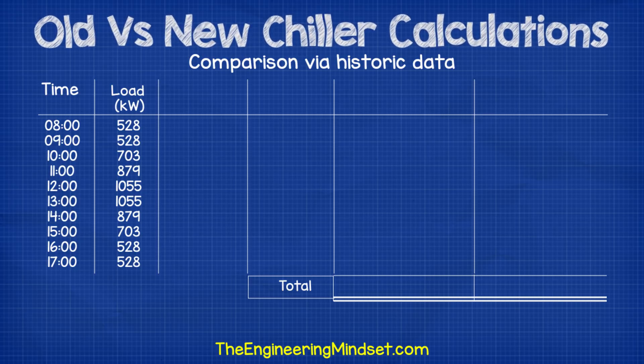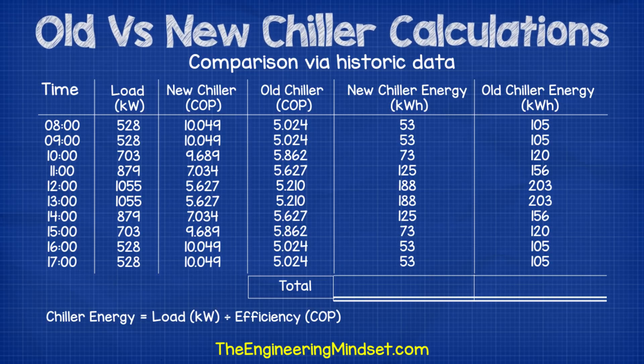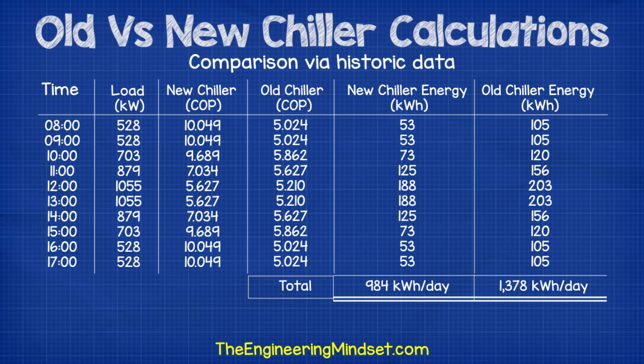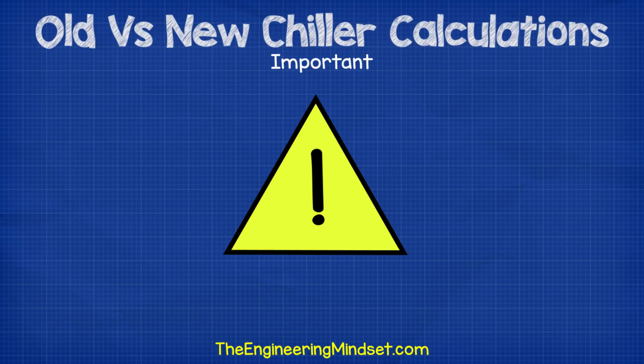If you have the cooling load in kilowatts, use the chiller COP — divide the cooling load by the COP value to calculate the hourly electricity consumption. Again, the replacement chiller would produce significant savings. This is an overly simplified example — in the real world, the chiller load will change throughout the day and the seasons and would likely run for much longer hours, so you need to account for this. Basing annual performance on a single day is simply not sufficient. You need to maximize the time and use accurate data.